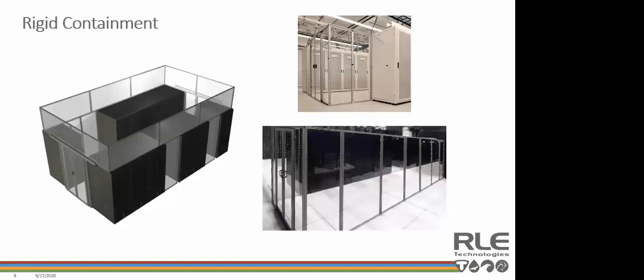Rigid containment is usually made up of clear or translucent rigid plastic sheets in an aluminum frame. Rigid containment is typically more expensive, but looks much more aesthetically pleasing. It's also more durable over time, at least in our experience we found it to be. The aluminum frame that holds the plastic sheets is usually black or silver, but RLE can have it anodized to match just about any color.